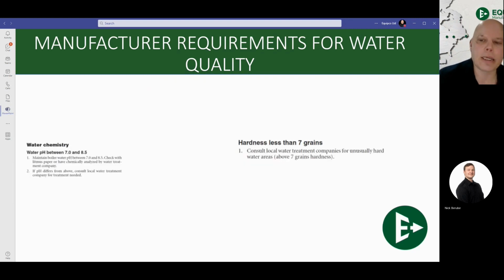Here's another example from a boiler manufacturer's installation manual, where they say again the pH between 7 and 8.5, and the hardness is to be less than 7 grains. So this is going to be different. This is the difference between a fire tube and a water tube heat exchanger as to what they will accept. It also goes to point that there is no magic bullet. There's no magic water that you can put into everything and it'll work, with the exception of demineralized. These things need to be checked and adjusted per each boiler manufacturer's installation instructions.